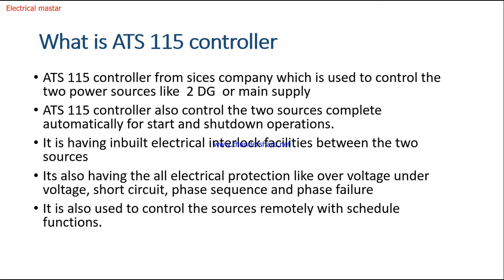Next, it can also be used to control the sources remotely with a schedule function. So not only the panel auto mode, it also has the schedule function application. Schedule function means once you put in the programming, like a weekly or monthly startup, then even at a remote location it will automatically start the generator, run it for your programmed hours, and then automatically switch off the generator.